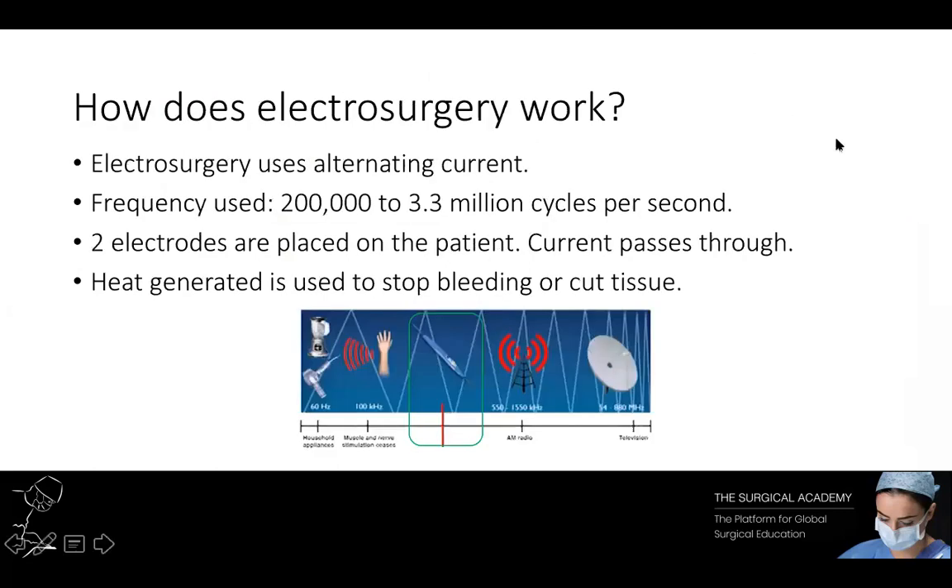Over the years, generators and equipment have evolved to make this technology safer for the patient and more efficient for the surgeon. Electrosurgery uses alternating current. We are familiar with this from the electrical mains, which in the UK is 240 volts with a frequency of 50 hertz. This type of current is potentially lethal if passed through the body. At 100,000 cycles per second — 100 kilohertz — electrocution doesn't occur and the current can pass through the body without obvious effect. Modern generators use frequencies of between 200,000 and 3.3 million cycles per second, approximately 20,000 times faster than domestic mains. As this frequency lies within the domestic radio band, it is frequently called radio frequency electrosurgery.